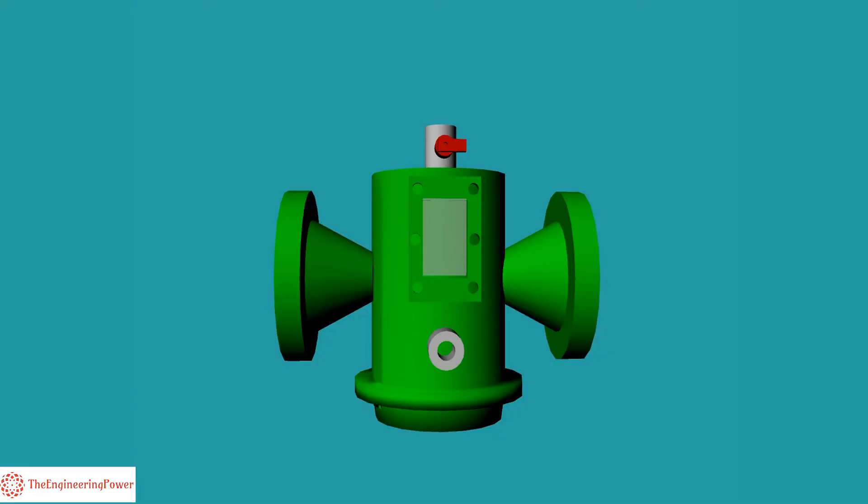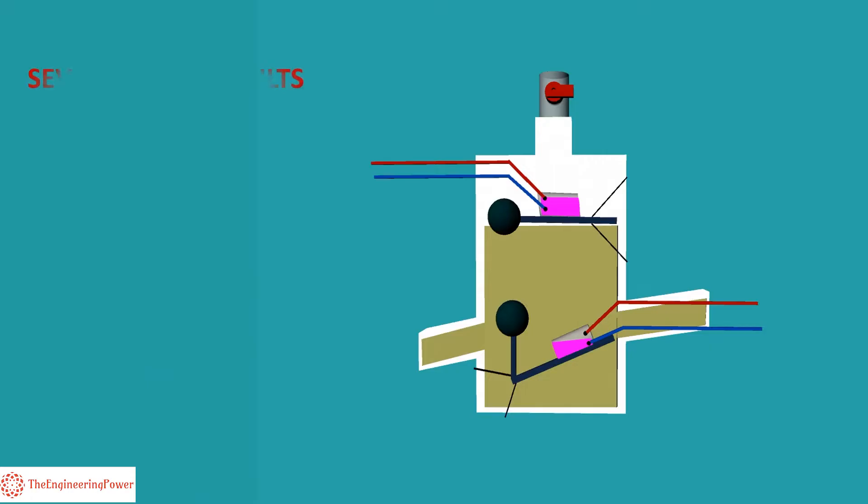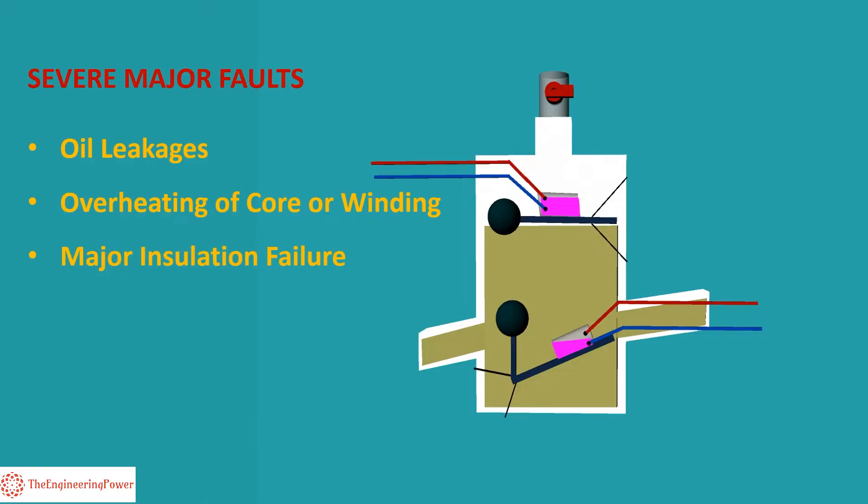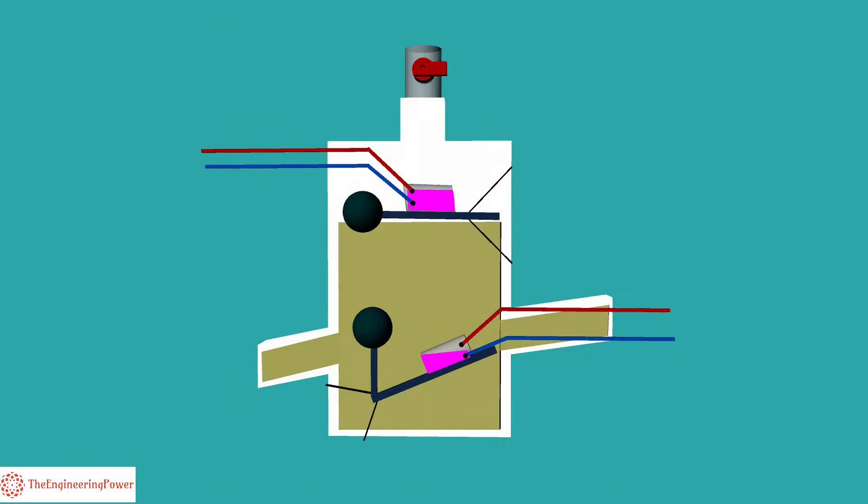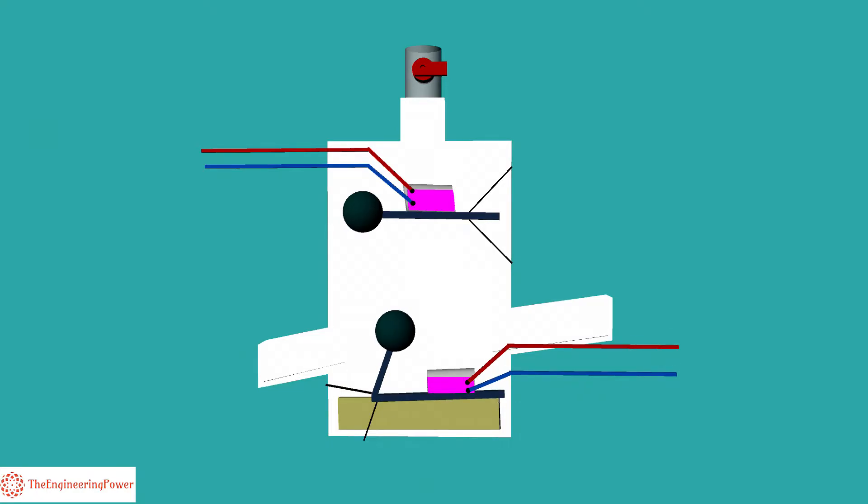Now we explain the working of the trip function of Buchholz relay. During severe major faults like oil leakages, overheating of core or winding, major insulation failure or fault in tap change equipment, oil level in the relay and conservator falls continuously, which results in tilting the lower float downwards causing the mercury switch to close and ultimately tripping the transformer.